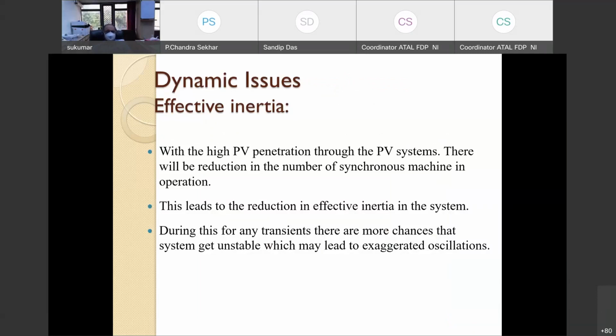Besides, as I have already mentioned to you, the inertia can be an issue because the photovoltaic system is in fact a static system and it does not rotate. Because it does not rotate, there is no inertia existing. And if there is no inertia, then the frequency becomes a variable quantity. And the dip in frequency, that is the nadir point in the overall grid frequency, will reduce and it may make the system desynchronized. Therefore, there are now many smart inverters coming where we are artificially producing this inertia, which is called synthetic inertia, to take care of this frequency variation of the grid.